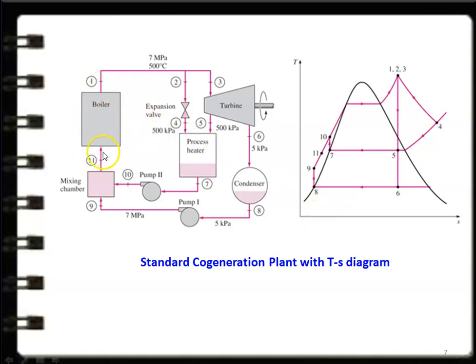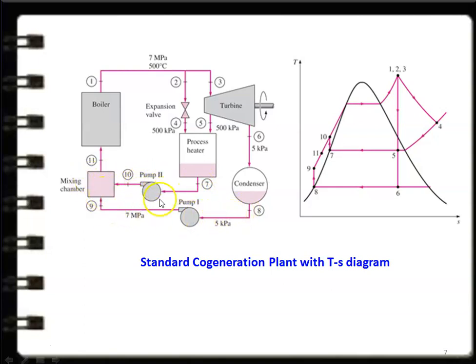In the standard cogeneration plant: the boiler produces high-pressure steam sent to both the turbine and the process heater via the expansion valve. The turbine exhaust is condensed, and the condensate is circulated back to the mixing chamber using pump 1. The outlet of the process heater is circulated back to the mixing chamber through pump 2. These two streams — both approximately saturated liquid — are mixed together and circulated back to the boiler.